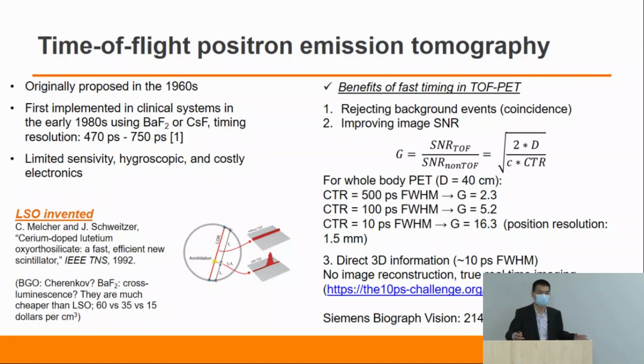Because the diameter of the PET system and the speed of light are fixed, we cannot change that for a system already developed. But we can improve the time resolution, the coincidence time resolution. For a whole-body PET system, the diameter is about 40 centimeters. If the CTR is about 500 picoseconds, the gain is about 2. The gain can improve to 5 if we improve the time resolution from 500 to 100 picoseconds. However, if we can further increase the time resolution to 10 picoseconds, we can have a gain as high as about 16. It's a very good improvement.